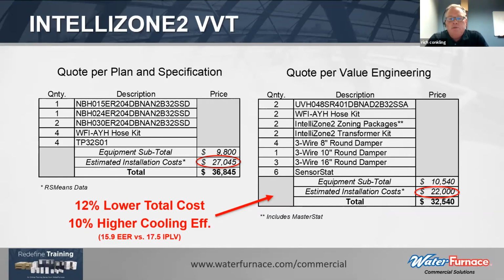But by eliminating 2 of those units, we're able to actually come in again a little bit over the initial design budget, but with the lower installation costs, we end up at a first cost installed 12% lower than we would based upon the current plans and specifications. We also, because of the variable speed nature of the product and the part load efficiencies, can go from an average 15.9 cooling EER to a 17.5 IPLV cooling efficiency. So a 10% increase in cooling efficiency, all at the same time that we're able to provide it at 12% lower installed cost in the system.